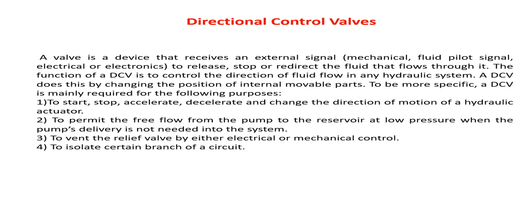To be more specific, direction control valve is mainly required for following purposes. The first purpose is to start, stop, accelerate or decelerate and change the direction of motion of hydraulic actuator. Second is to permit the free flow from the pump to reservoir at low pressure when the pump delivery is not needed into the system. Third purpose is to vent the relief valve by either electrical or mechanical control, and fourth one is to isolate certain branch of a circuit.